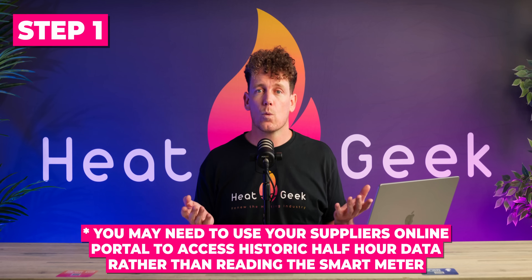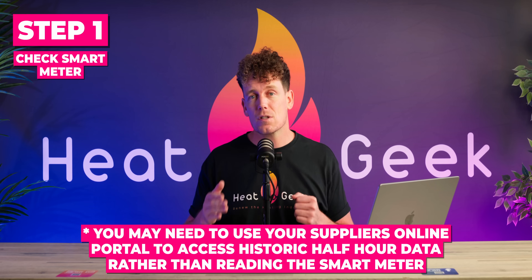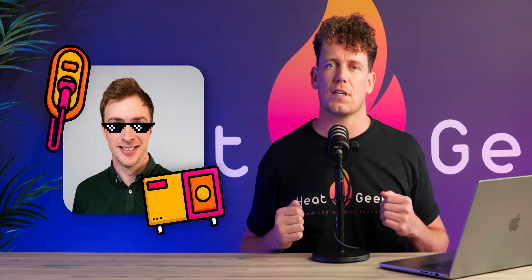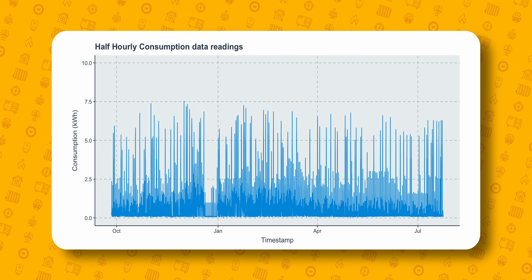Here are our recommendations for what you could do as a competent engineer in domestic homes. The first step would be to check the property's smart meter. Some smart meters give historical data down to half-hourly resolution, and if yours doesn't, you can also connect to a system like Loop — others are available — which will give access to half-hourly data. From here, it's actually pretty easy to determine the maximum demand. Our data scientist Mikey Harper owns a property which has a car charger and a heat pump, so is a much higher than average user of electricity, and his home shows a maximum energy use of 7.5 kilowatt hours within a half-hour period.